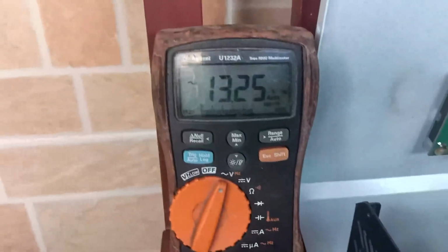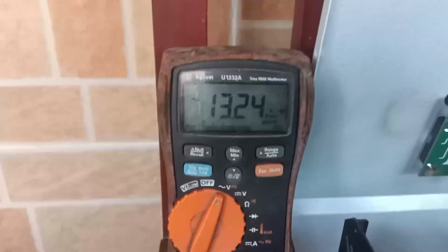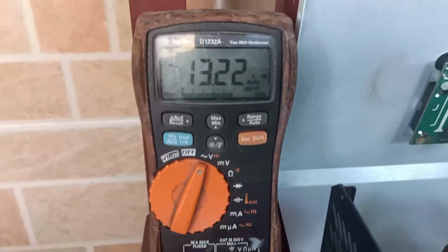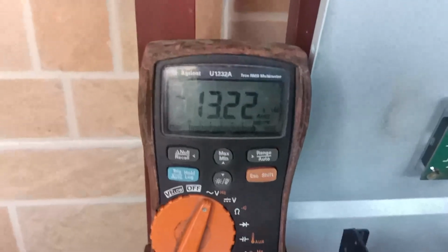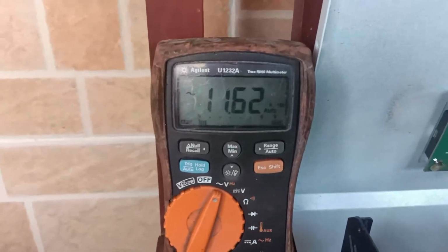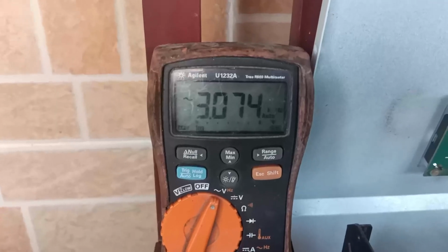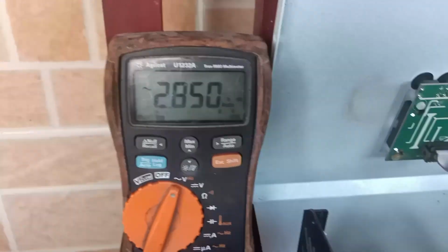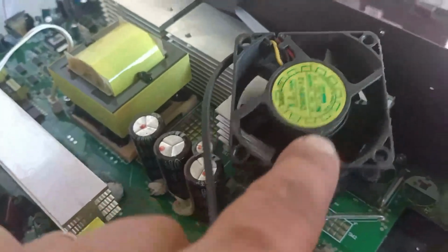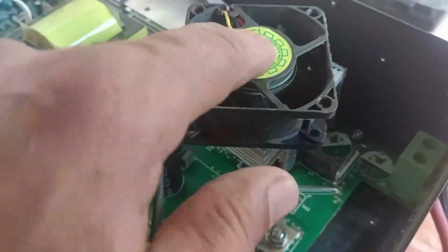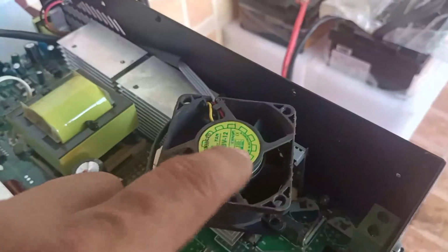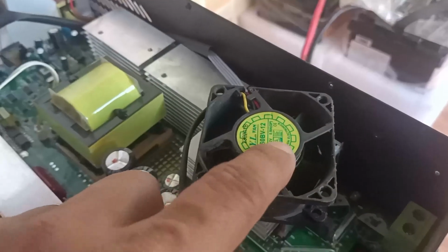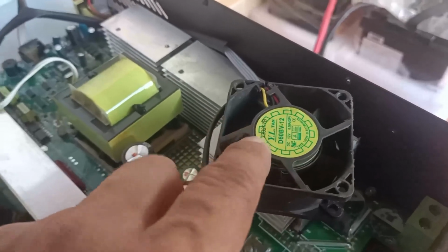I don't think it should be 13 kilohertz. The speed of the fan is not 13 kilohertz, so the motor can't run at 13 kilohertz. Multiply that by 60 and it will give you the RPM. It's not giving you that RPM. These are brushless, and there's a Hall sensor in here that senses the rotation of the fan, then it pulses out and is detected by the computer.